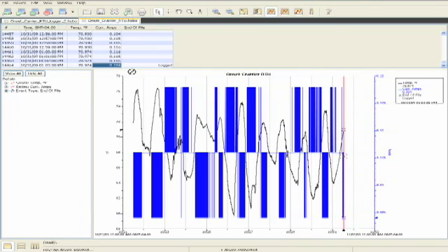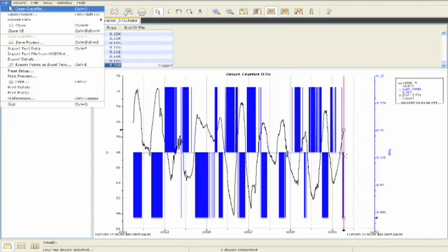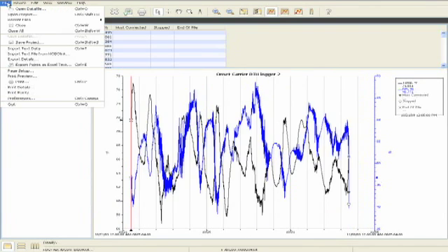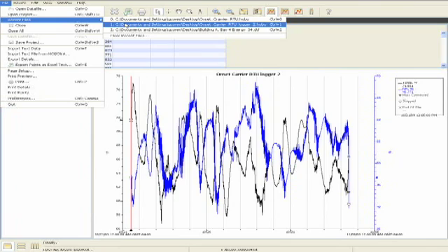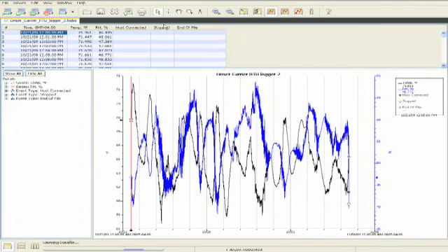So temperature, amperage. That was logger number one, supply air temp and compressor amperage. Again, there was more or less a zero across the board on the compressor amperage and supply temp anywhere from 76 down to a couple of nights of 59, 60 degrees. So when we're done with this project, we will close this one out, go back in some of our recent files and load logger number two.